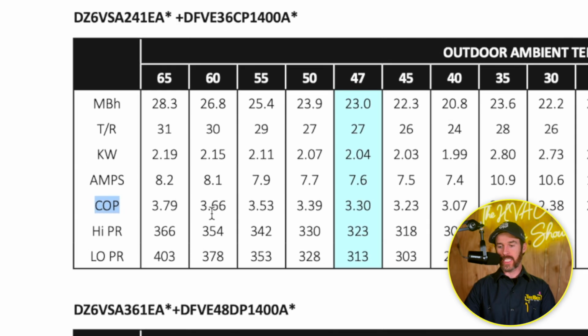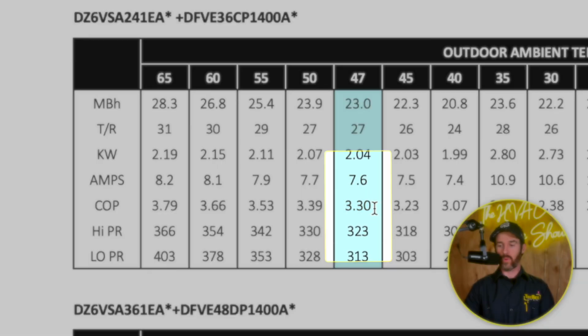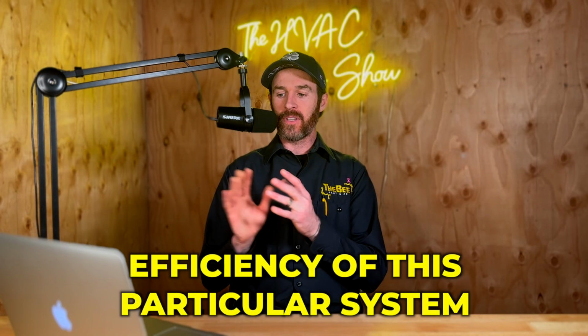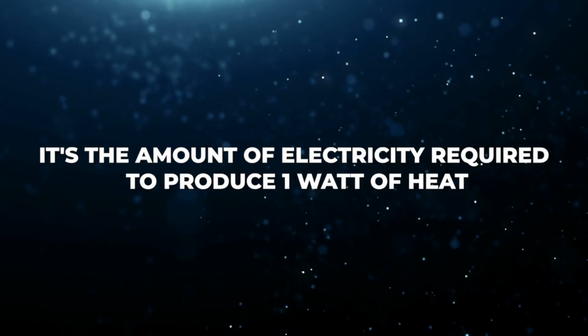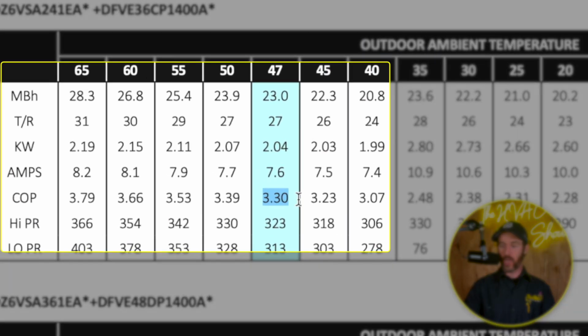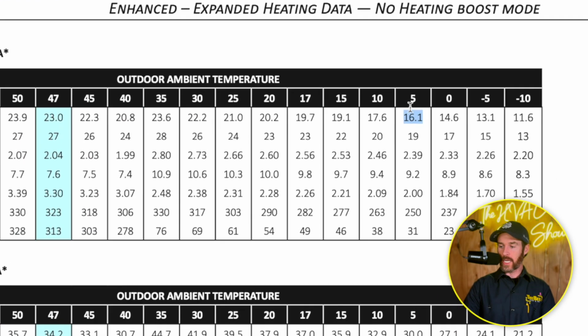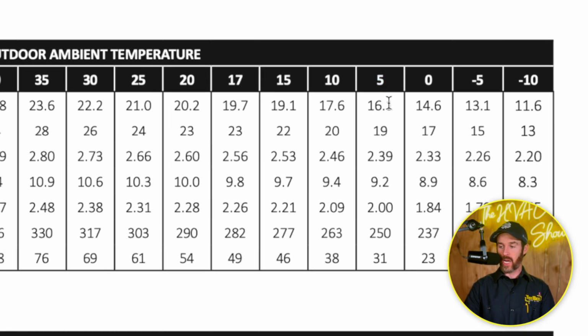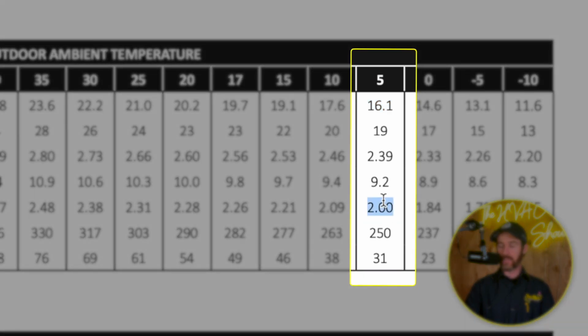And scrolling down here, this COP stands for coefficient of performance. And so this number, 3.3, is the efficiency of this particular system. What a COP means is the amount of heat produced per watt of electricity. A COP of 3.3 means that it takes 1 watt of electricity running the heat pump to produce 3.3 watts of heat energy, because a watt is also a measurement of heat, not just electricity. So you can see this COP of 3.3 at 47 degrees Fahrenheit, and the output is 23,000 BTUs. If we scroll down to see how the system performs at 5 degrees Fahrenheit, we can see that the capacity loss is such that it is producing 16,000 BTUs of heating capacity, and the efficiency drops as well.